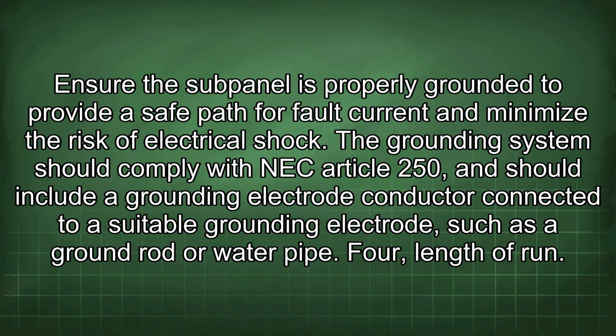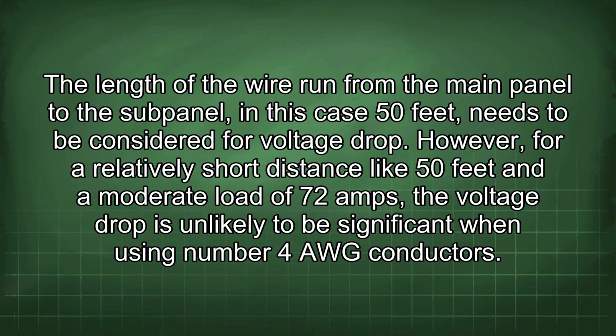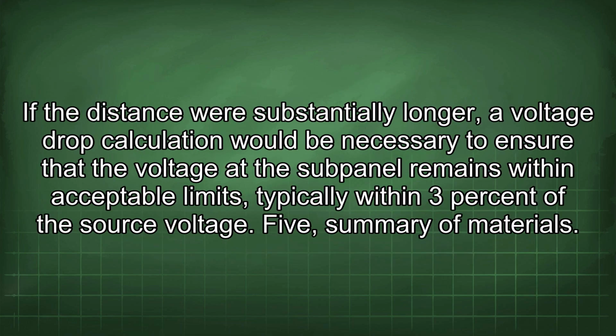4. Length of run. The length of the wire run from the main panel to the subpanel, in this case 50 feet, needs to be considered for voltage drop. However, for a relatively short distance like 50 feet and a moderate load of 72 amps, the voltage drop is unlikely to be significant when using number 4 AWG conductors. If the distance was substantially longer, a voltage drop calculation would be necessary to ensure that the voltage at the subpanel remains within acceptable limits, typically within 3% of the source voltage.